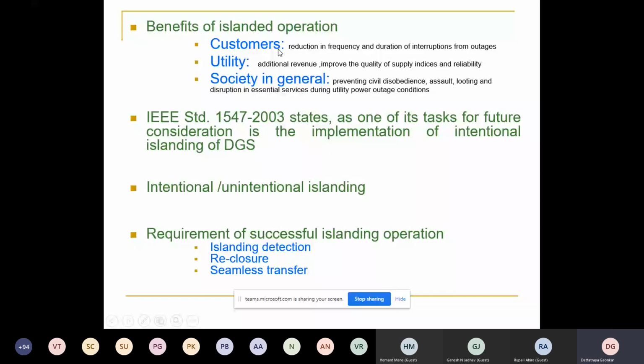Okay, the customers get benefited, because when there is no supply from the grid, the DG is supplying, and the DG owner and utility can earn. And IEEE has now come up with an improved version of the earlier standard, the IEEE 1547 2018 standard, which says all your grid-tie inverters must have islanding detection capability. They should be able to operate in islanding mode. Right now, all grid-tie inverters do not operate in islanding mode.